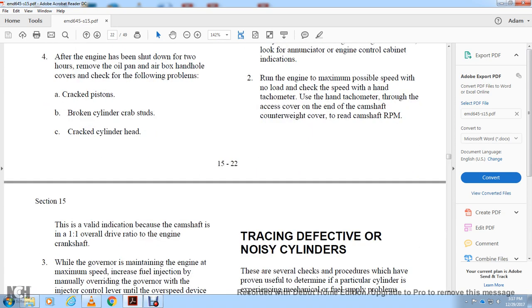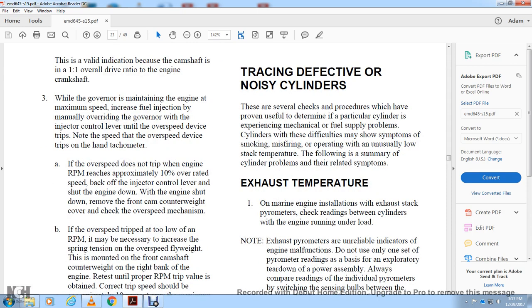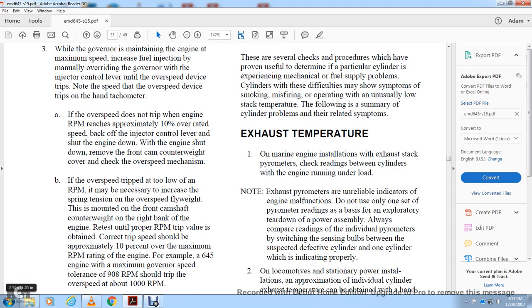While the governor maintains the engine at maximum speed, increase fuel and manually override the governor with the injector control lever to reach the overspeed device. Note the speed the overspeed device trips using a hand tachometer. If the overspeed device does not trip, the RPM will reach approximately 10% over rated speed, at which point the injector control will shut the engine down. With the engine shut down, remove the front camshaft counterweight cover and check the overspeed mechanism. If the overspeed trip setting is too low, increase spring tension on the overspeed flyweight mounted on the front of the camshaft counterweight, right bank of the engine. Repeat until the correct RPM trip value is obtained — trip speed should be approximately 10% over maximum RPM rating.